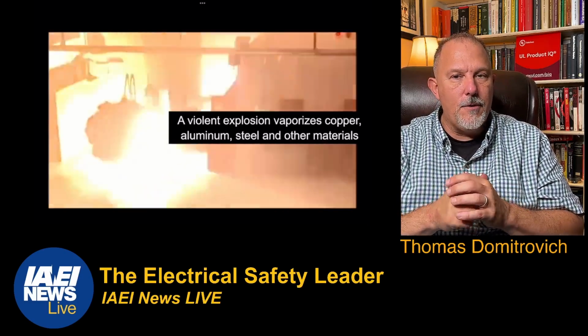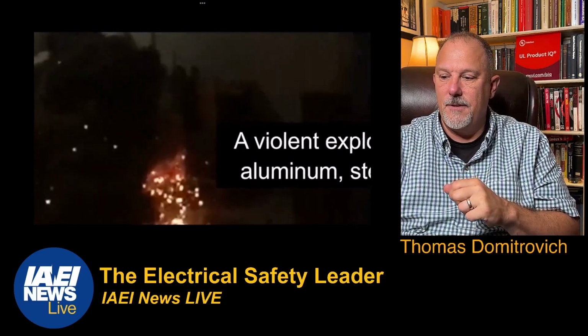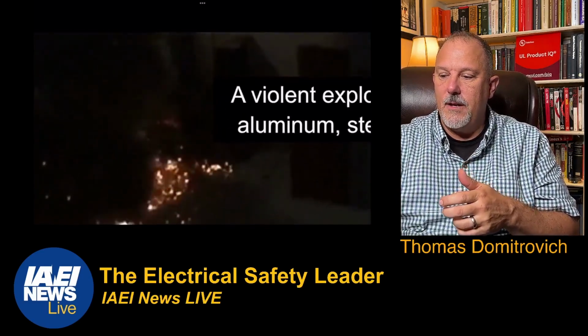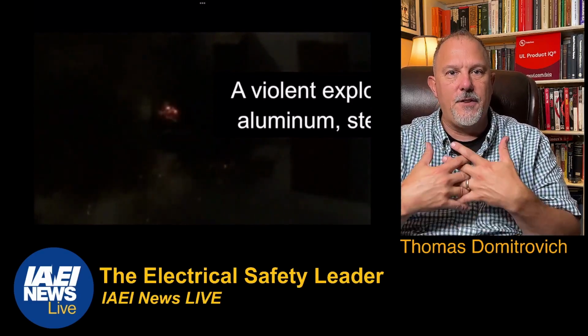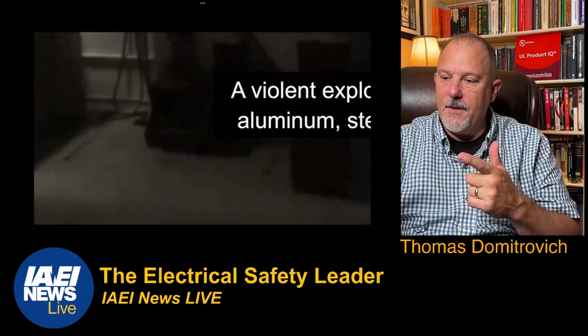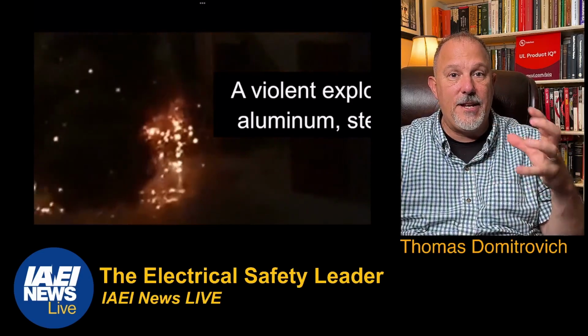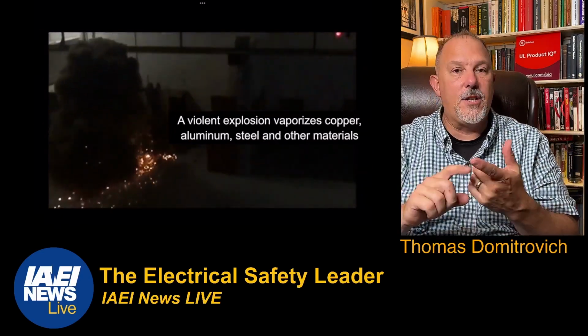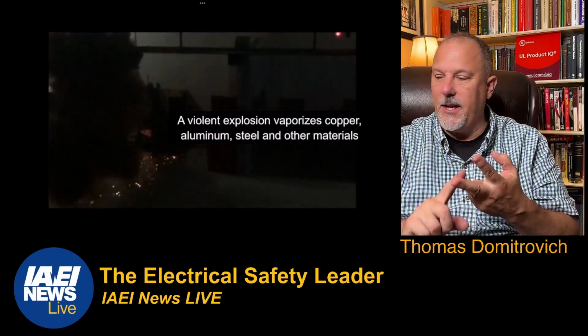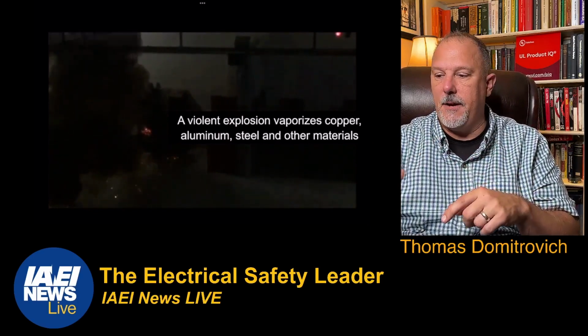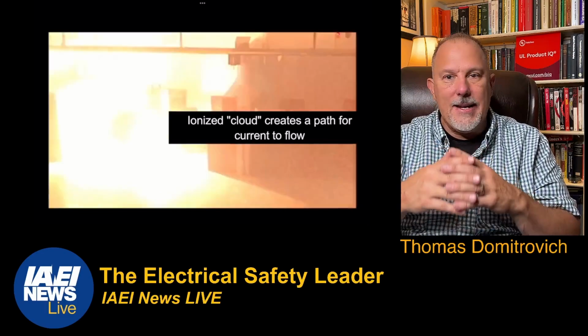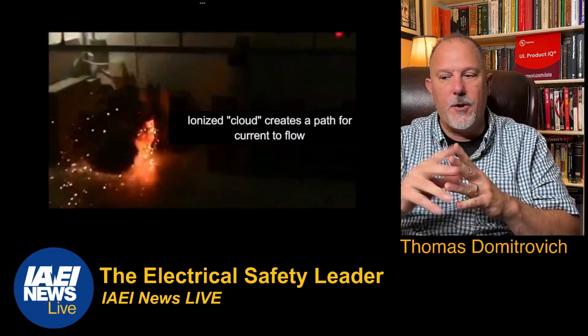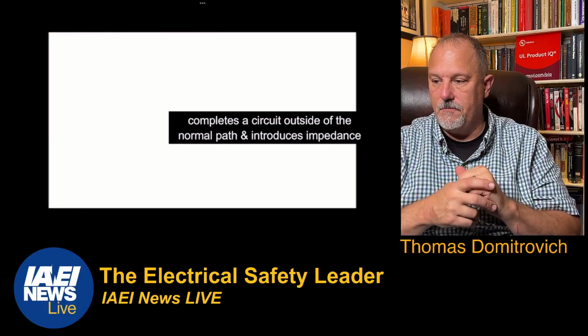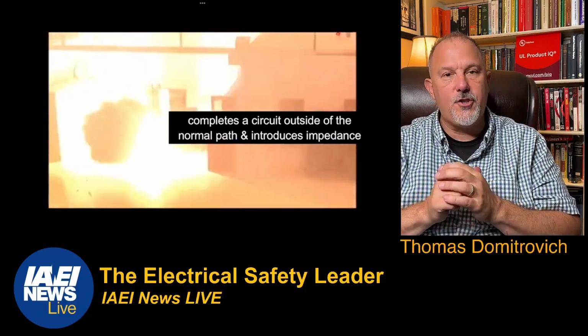So there's your plasma cloud, right? That plasma, that bright event, when we initiate an arc flash event, that light, that gaseous cloud is your plasma. That's the vaporization of your aluminum, your steel, any other plastics that might be in there. That ionized cloud, again, creates a path for current to flow, and it introduces an impedance.